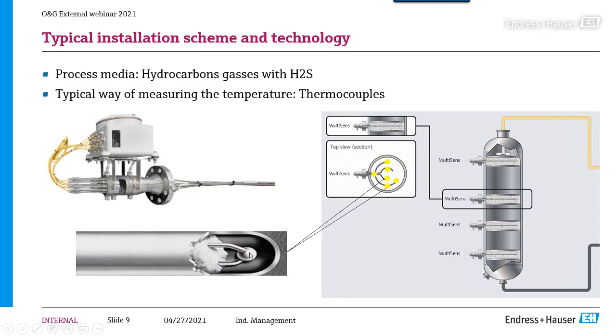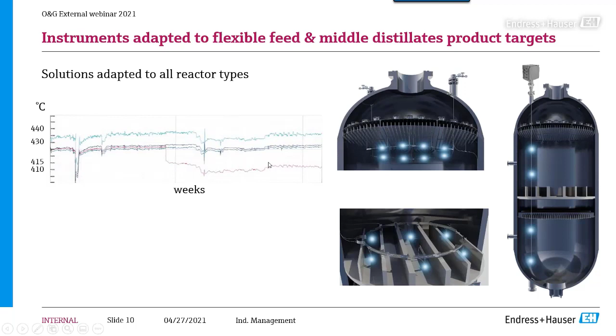Here are some examples again about data from the field, where we see exactly what happens when a thermocouple drifts. You can see some temperature values over many weeks, months, or even more. If you look at this red line, you can see that almost from one day to the other, there was a drop of about, I would say, 10 degrees. That's really something strange, because all the other thermocouples did not show the same behavior. And this is for us a typical sign that something might happen.